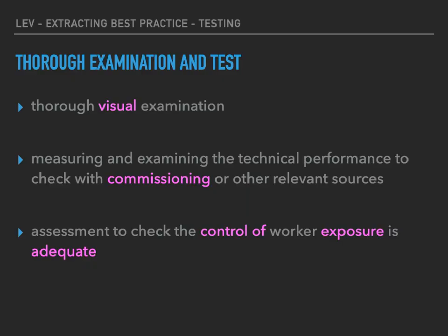When the tests are carried out, the big complaint is that they're not done thoroughly. It is a thorough examination and test, normally carried out in 3 stages. The first is a thorough visual examination to verify the LEV is in efficient working order, good repair and clean condition. You're looking for dents, damages and holes in filters, and checking that operators are using it properly, and that flexible hoses aren't crushed.